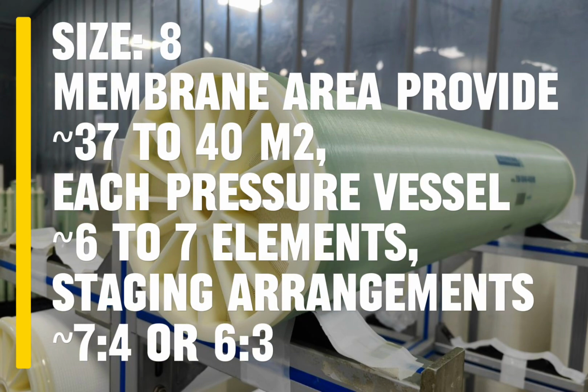Then he understood membrane design, where the typical element size is 8 inches. Each element provides about 37 to 40 square meters of membrane area, and each pressure vessel usually contains 6 to 7 elements, with staging arrangements like 7:4 or 6:3 to optimize performance.